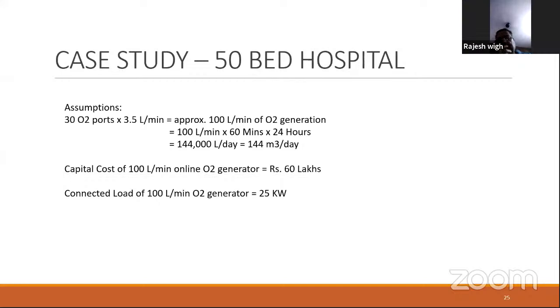So I had done a calculation for a simple 50-bed hospital, assuming this small hospital is in some remote place where oxygen is never available anyway. Out of 50 beds, let's say 30 ports have oxygen ports where you require 3.5 liters per minute of oxygen. Normal flow rate is about 2 liters, but currently with the COVID situation, you have to design for a higher flow rate.